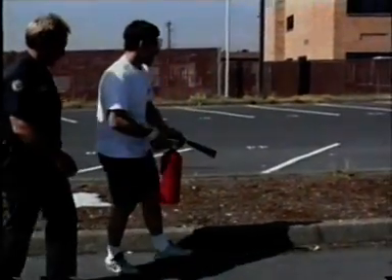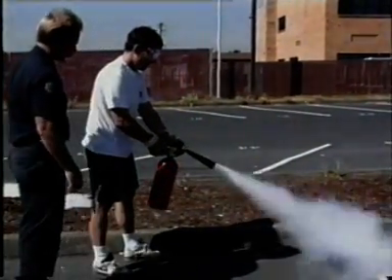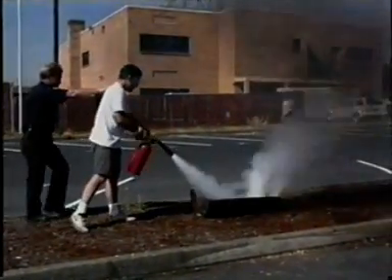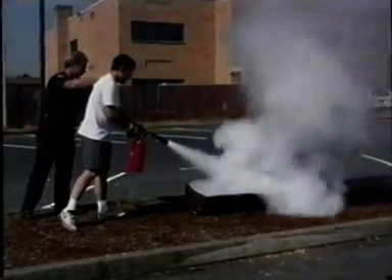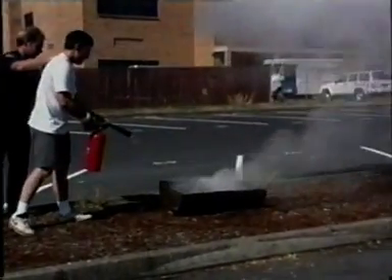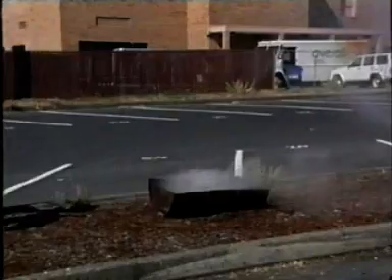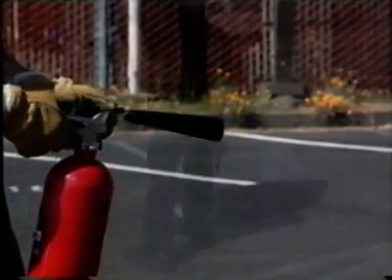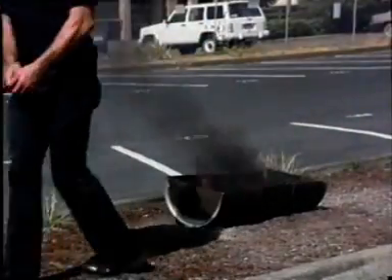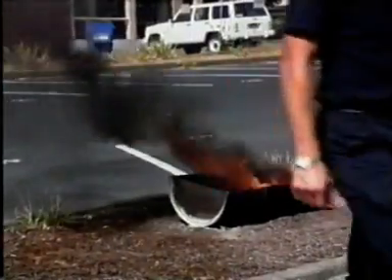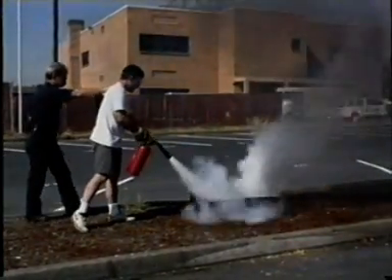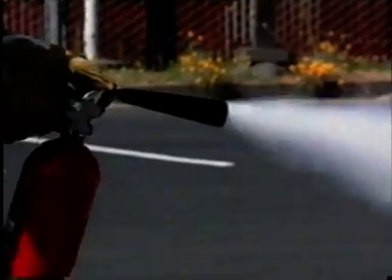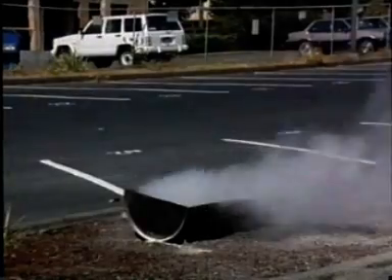Prepare to squeeze the shutoff handle while pointing the discharge horn at the base of the fire. Be aware that CO2 extinguishers are very loud when they expel the agent. Also, keep your hands on the handle in back of the discharge horn because the discharge is very cold and can cause freeze burns. On flammable liquid fires, it is best to sweep the flame from the burning surface, starting at the near edge of the fire and moving forward. Continue to apply the discharge after the flames are extinguished to prevent a reflash.